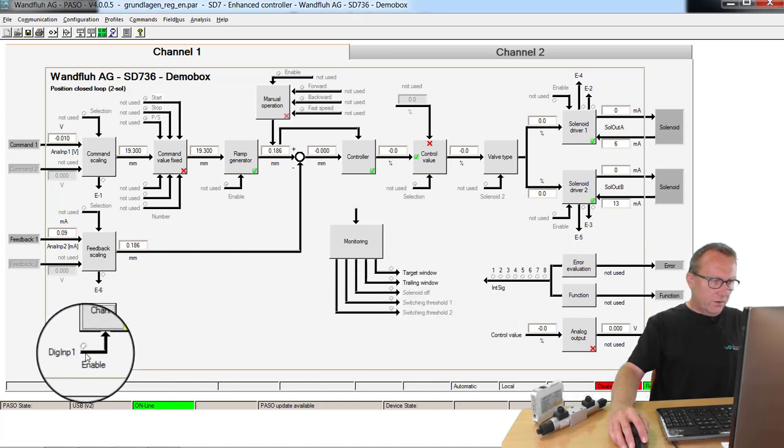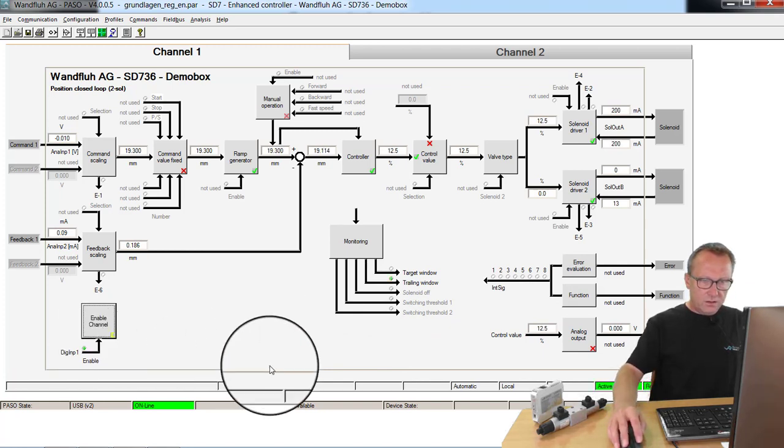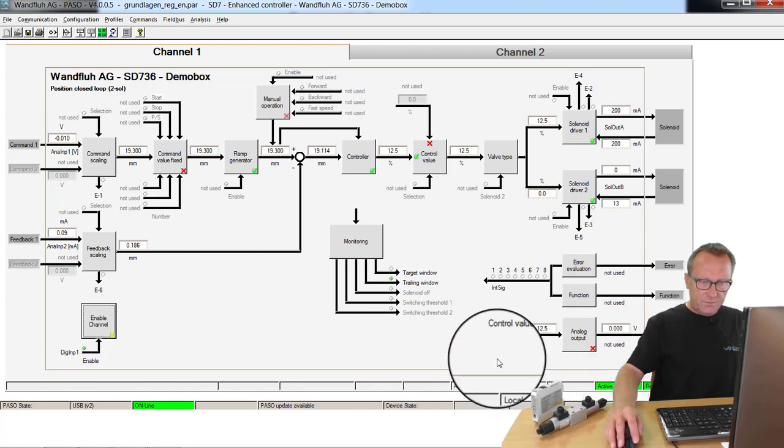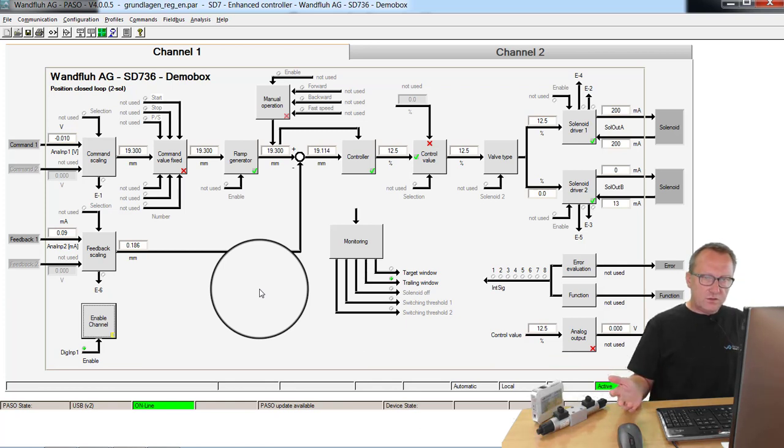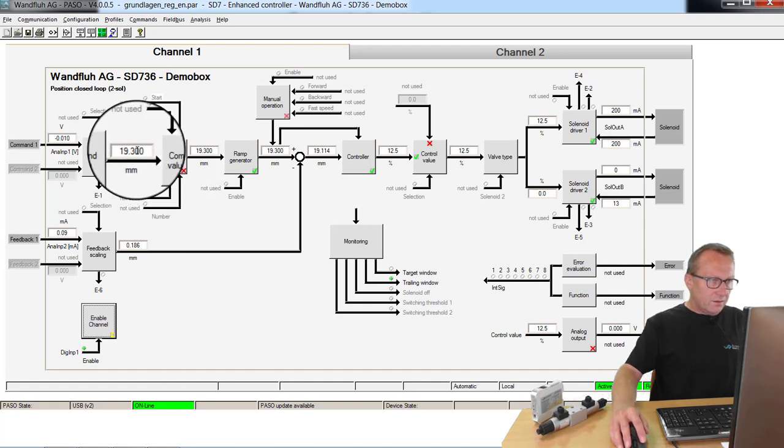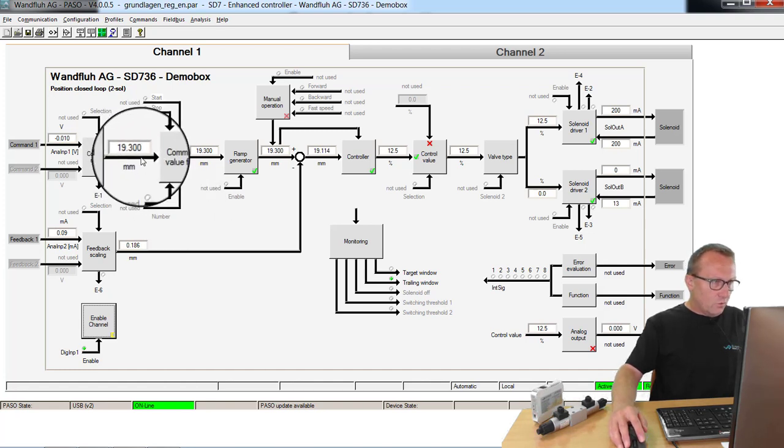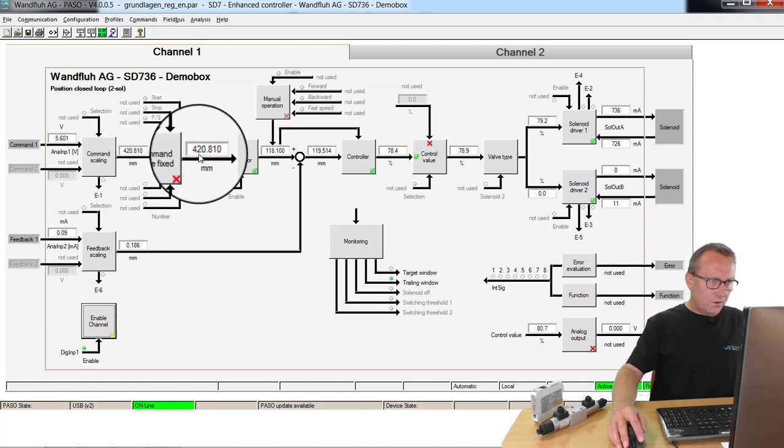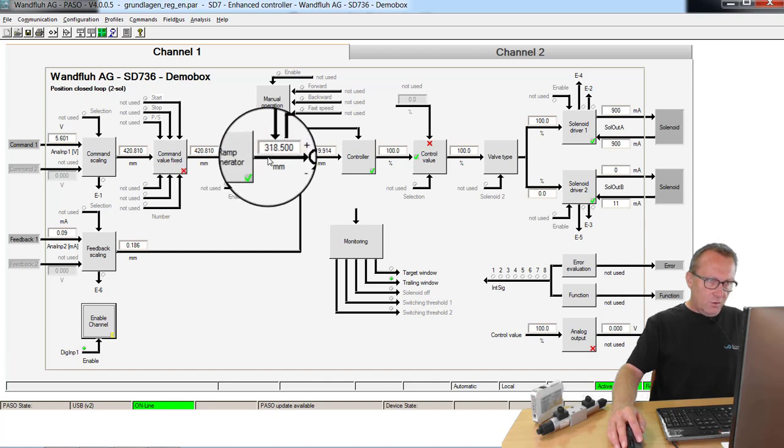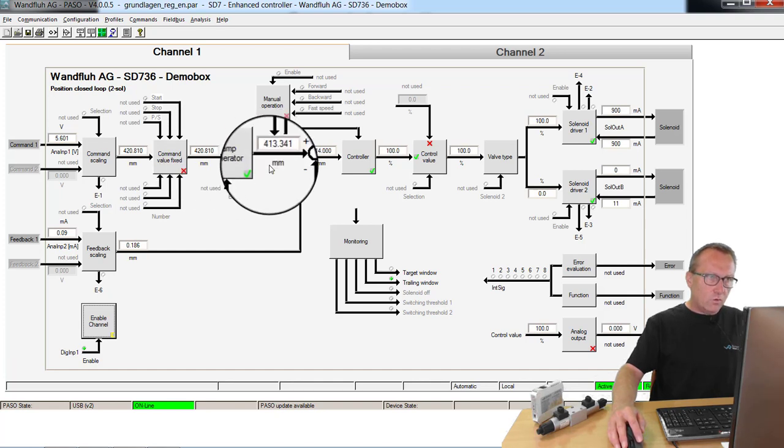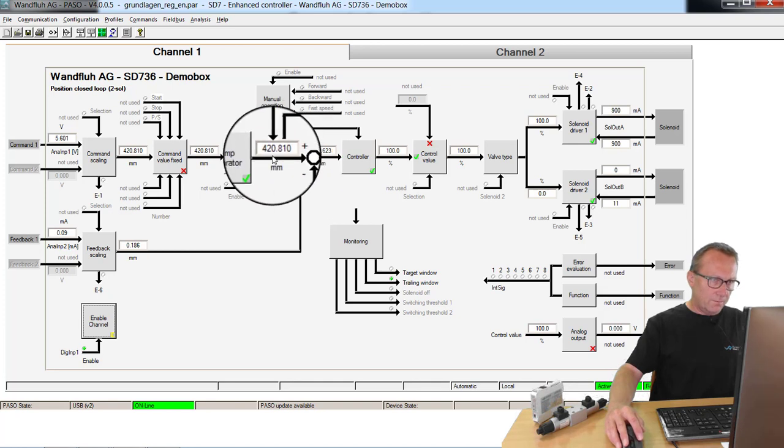Now if I activate digital input 1, my card is released and the controller is switched on. If I give now a new command value, for example 420 mm, the command value will move with adjusted speed to this value.